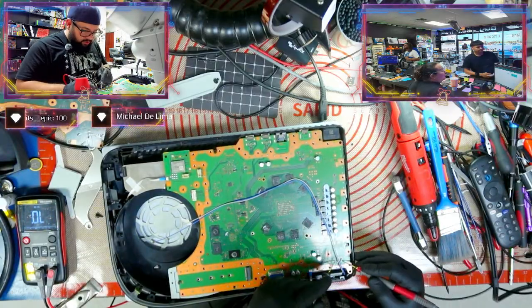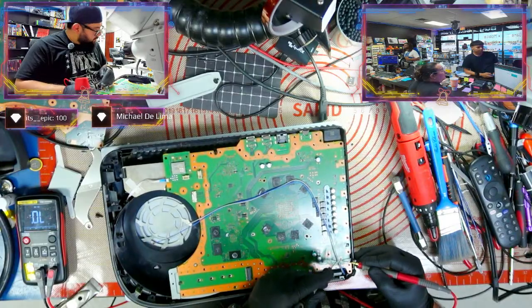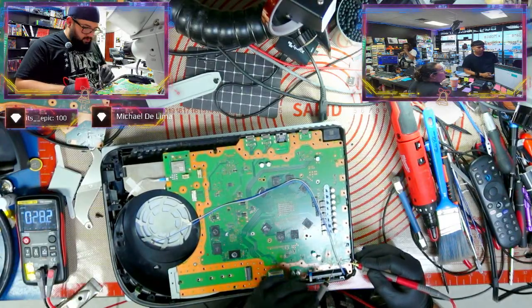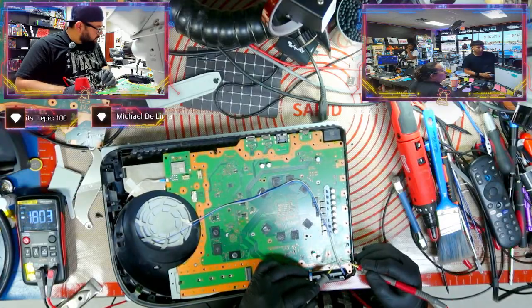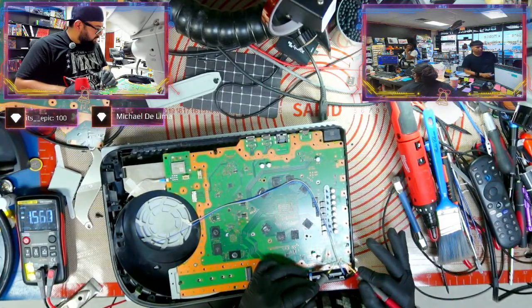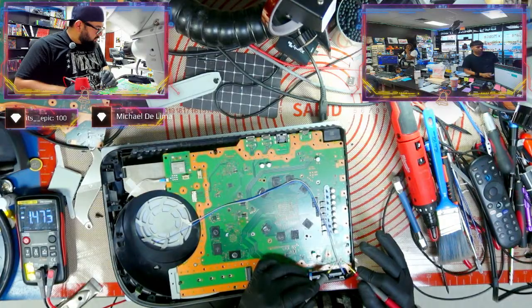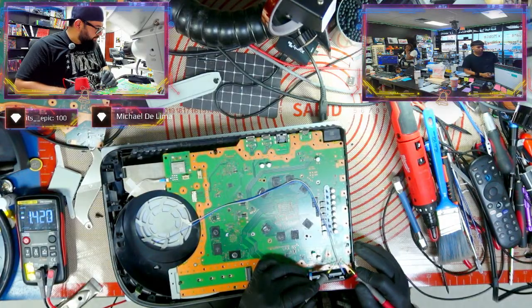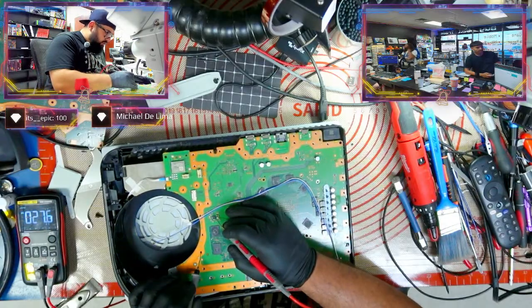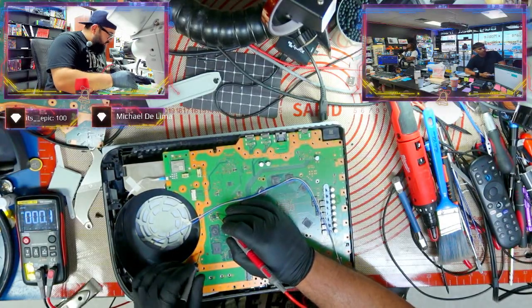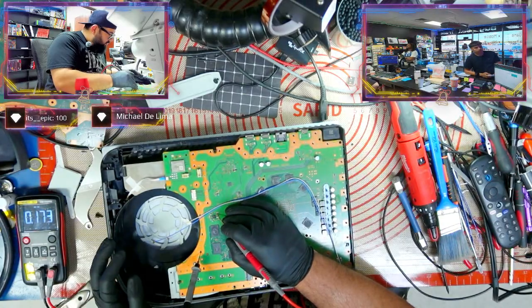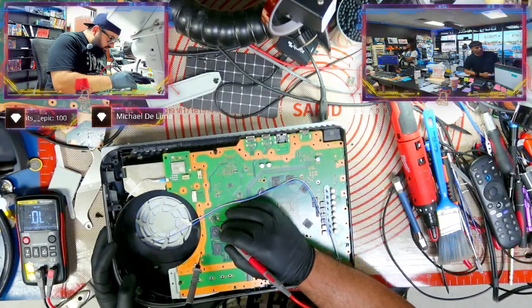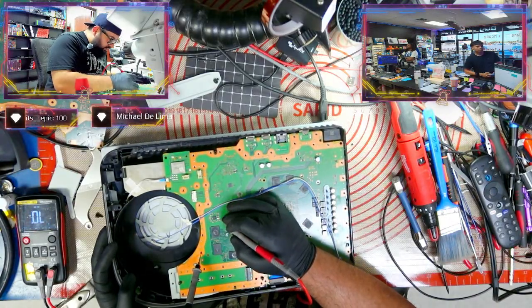Let me make sure we deplete this real quick. Need to make sure we deplete power from here, and then we'll test again. It's being depleted. It says this is short circuit, but I tested earlier and it wasn't. It's not short circuit, however, it's not getting voltage.